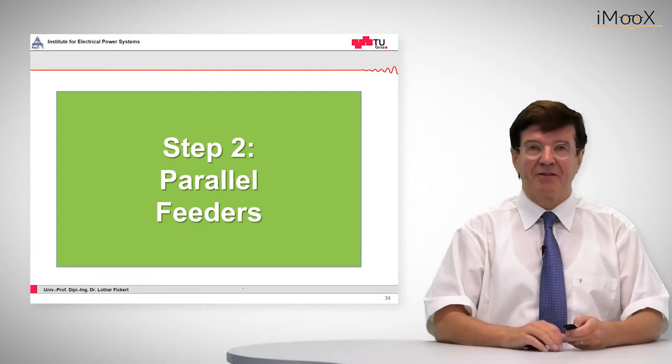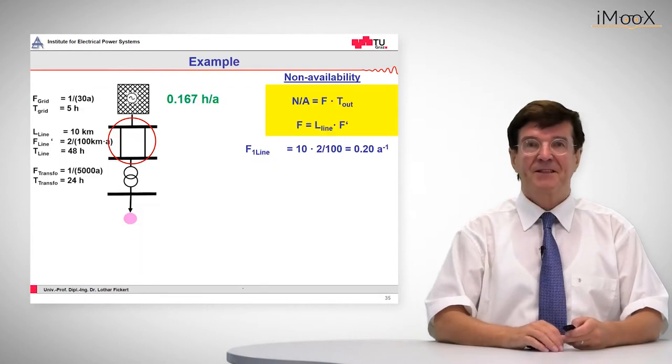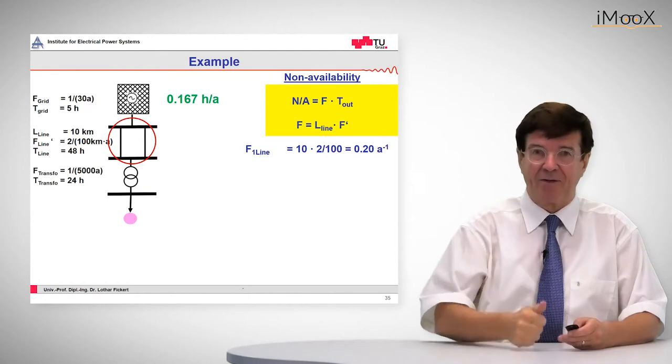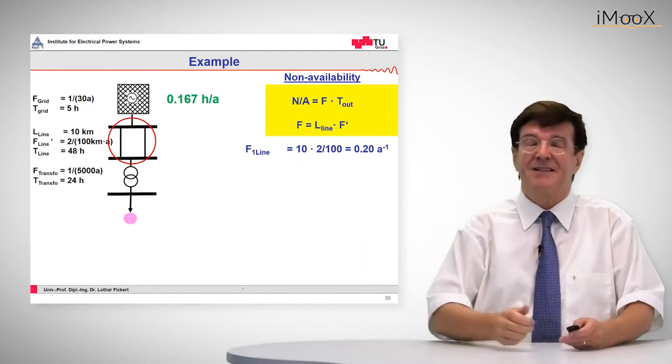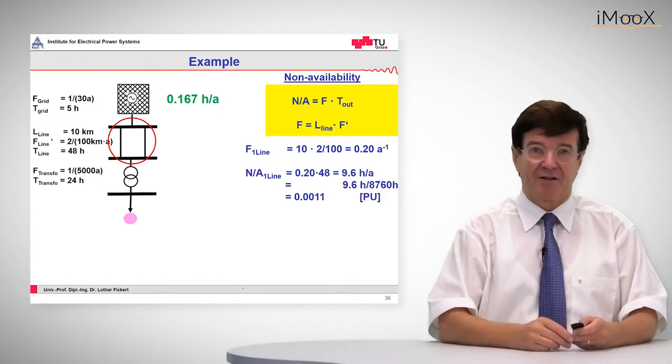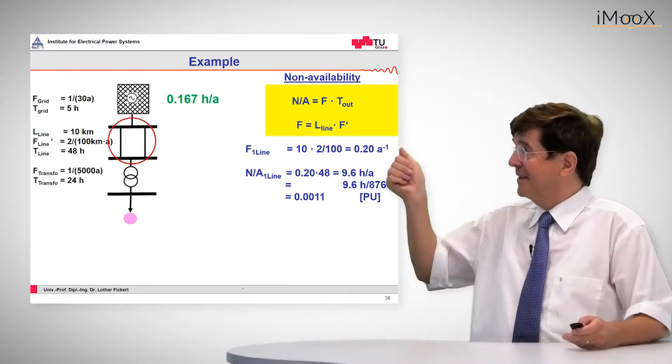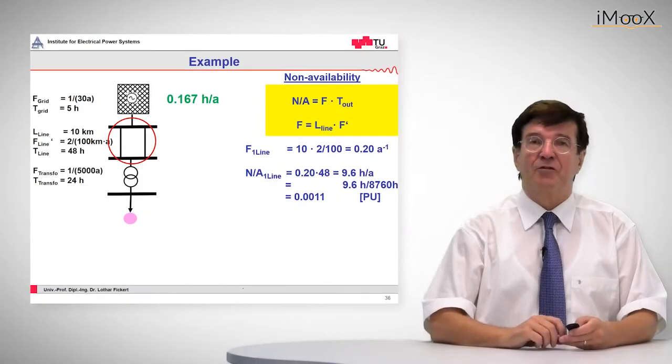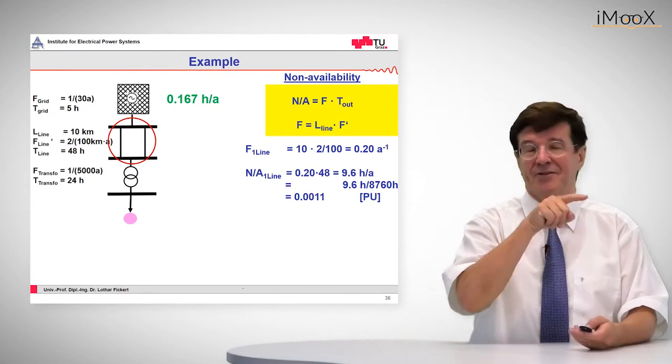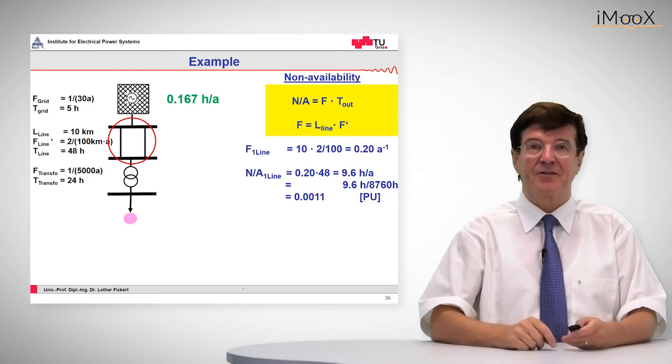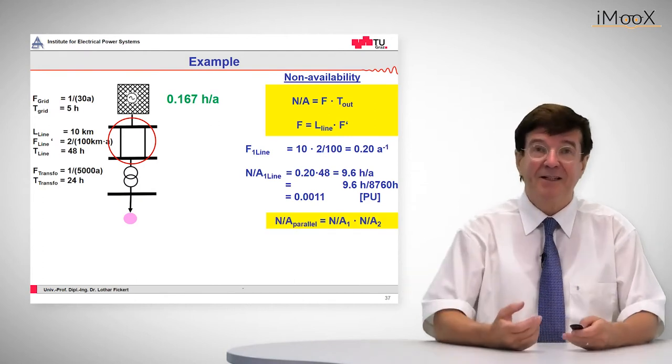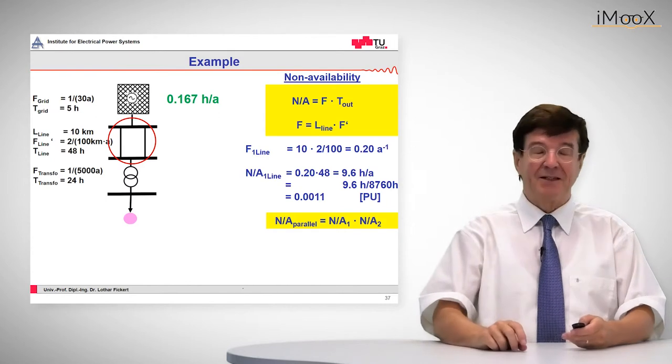The next step is to determine the non-availability of the parallel feeders. The non-availability of feeder 1 is 0.20 per year times the average time, which comes out as 9.6 hours per year. For a specific reason, I turn this into a per unit expression by converting one year into 8,760 hours, arriving at 0.0011. The reason is we have to multiply the non-availability of line 1 with line 2, which is conveniently done using per unit quantities.